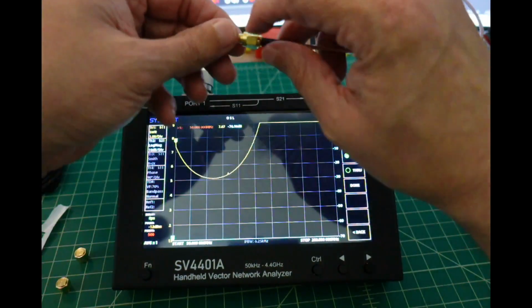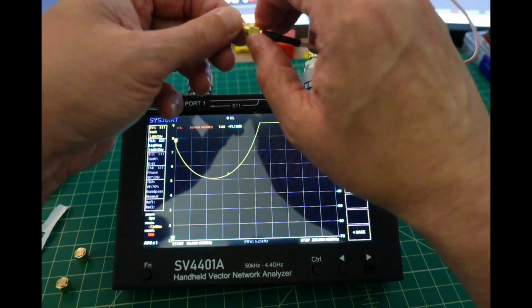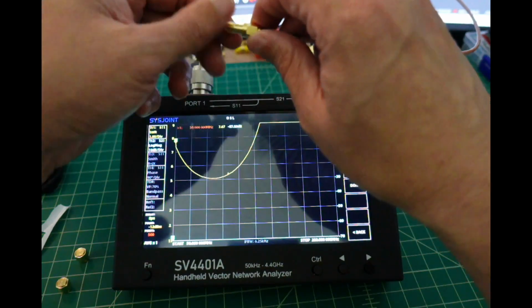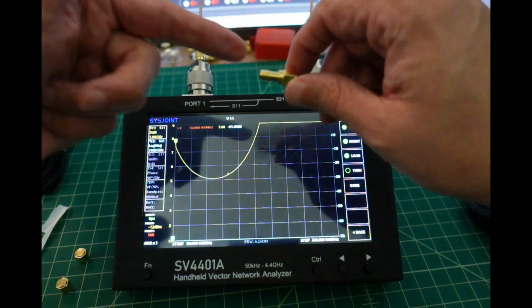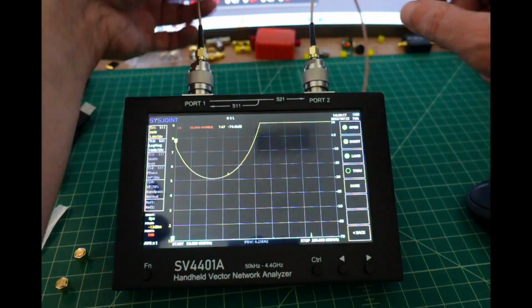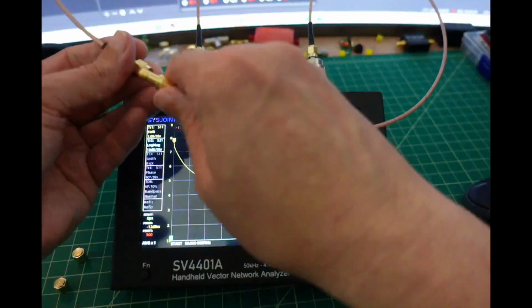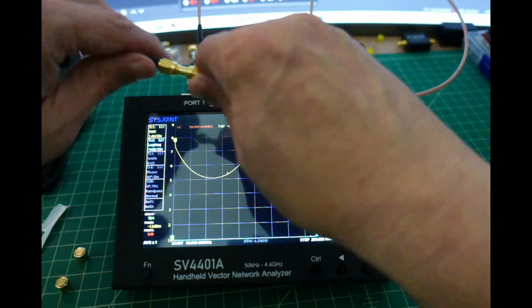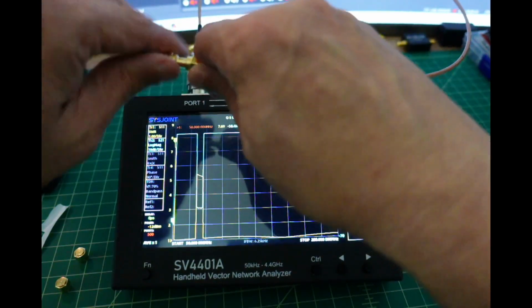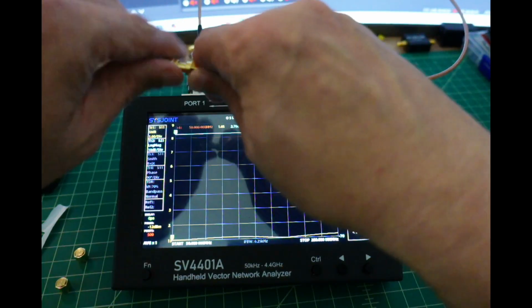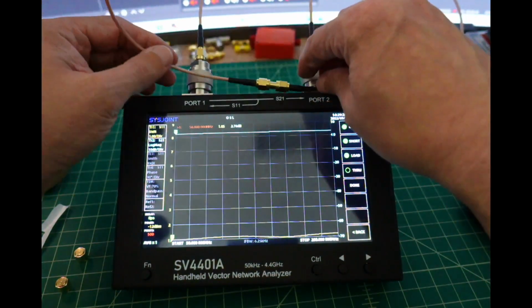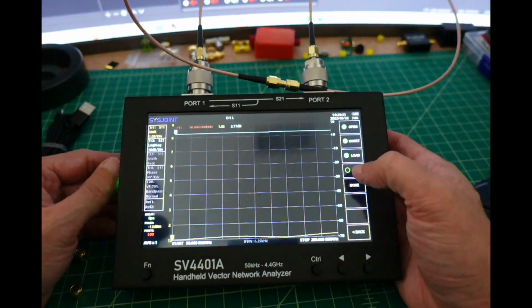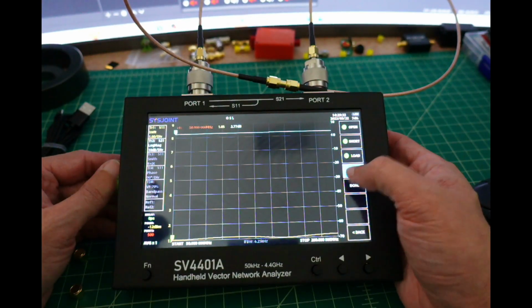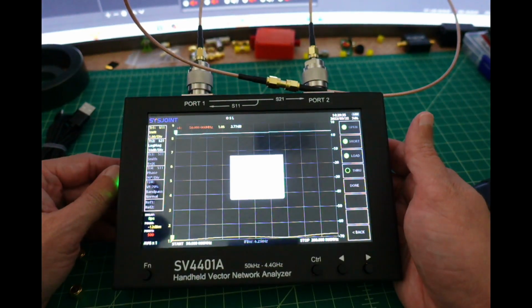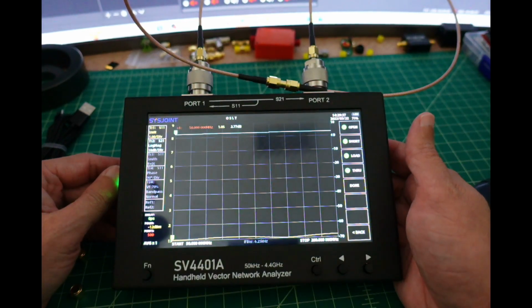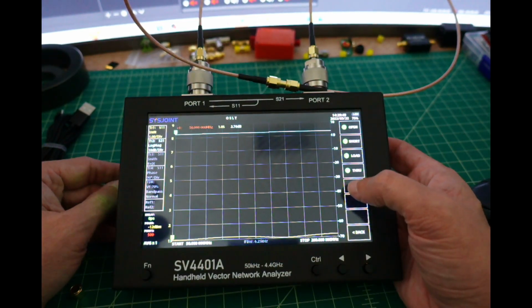When you put these on, you want to turn these at the hexagon or the nut end and not spin the barrels, because the barrels will spin along your center conductor inside and can limit the life of your cable. These cables are pretty cheap, so if you do limit the life, it's not the end of the world. Okay, so now we have our through calibration set up. I'm going to go ahead and hit this button. Okay, now we're done. I'm going to go ahead and hit the done.